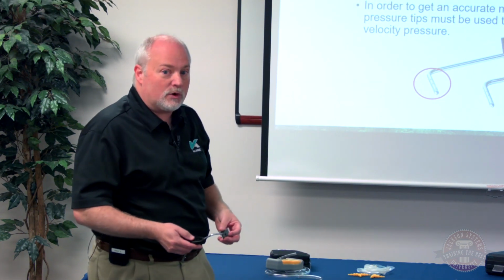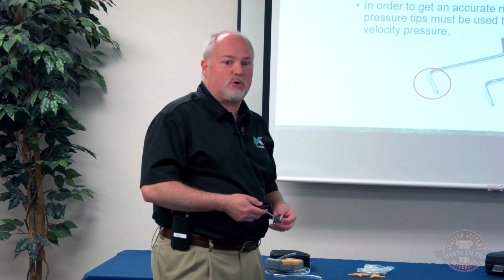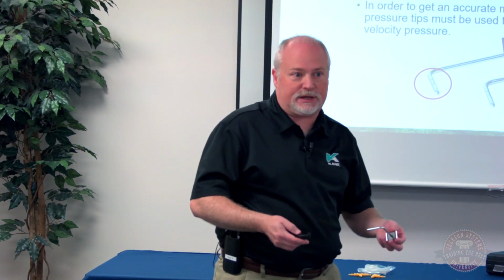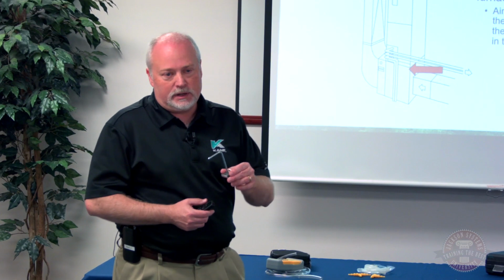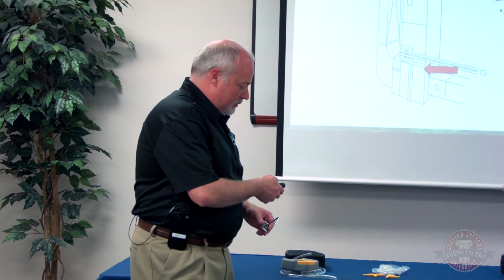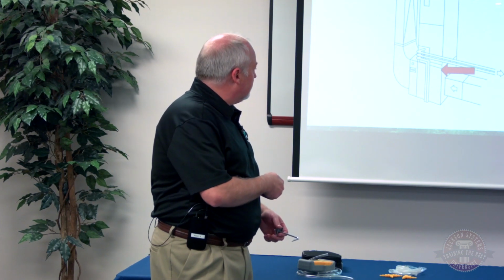Now, the type of equipment we're working on is going to determine where we want to place those probes in the system to get an accurate reading. A quick and easy way to remember this is you want to measure the equipment for external static pressure as it was shipped. So in this first picture here, we have an air handler. Typically our air handler has the coil built into the unit. So when we get that air handler, you've got the blower section and the A coil is in the air handler. So when the manufacturer has tested that piece of equipment and rated its CFM airflow with the external static pressure, it's done with that A coil in place.